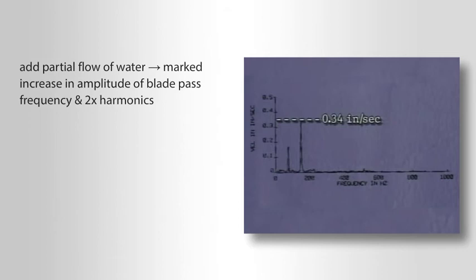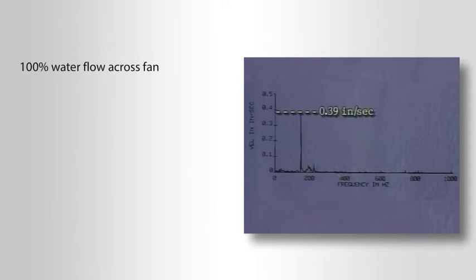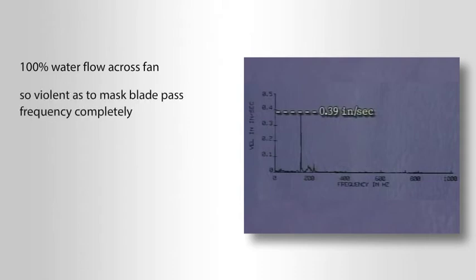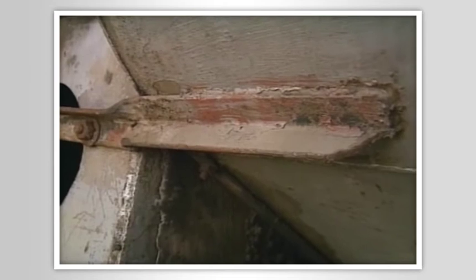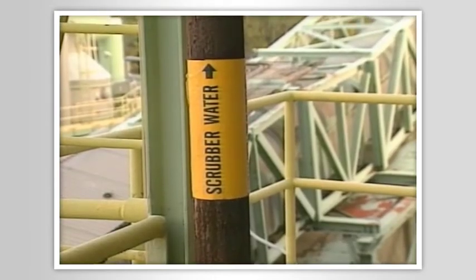When we begin to add a partial flow of water, we see a marked increase in the amplitude of both the blade pass frequency and the two-times harmonics. By the time we reach 100 percent water flow across the fan, the two-times harmonic, which now reaches above 0.3 inches per second, has become so violent as to mask the blade pass frequency completely.